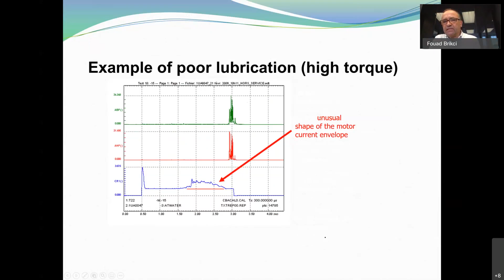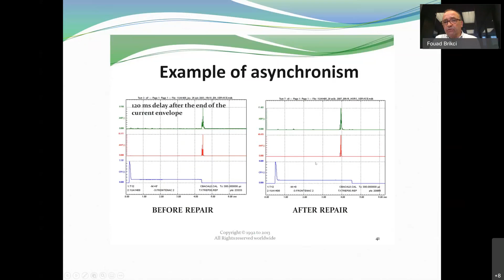An example also of asynchronism. Here on the left, you can see that the impact means that the transition of the tap changer comes at the end of the current. Sometimes it's dangerous because the tap changer could stay between two taps, and this is not good at all. And here, after repair, we have done an adjustment of this impact.